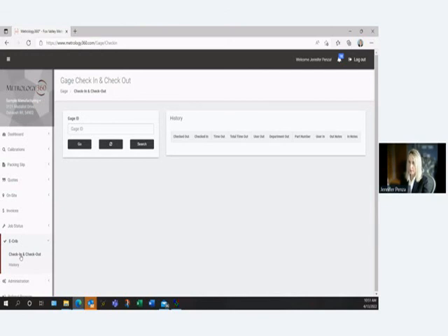There's traceability for jobs. When you do jobs and you check a gauge out for that particular job, there's traceability on what gauges were used on that job. So the sky's the limit here, guys. We can use this tracking for anything because the actual history is where the real power of this tool resides. It's simply logging in and logging out, and data populates. We're finding some people are using this for a trend on calibration. Instead of just calibrating every 6 months, they calibrate it after so many uses because they're finding it falls out of tolerance after 150 uses. So there's a lot of different ways that you can do this.